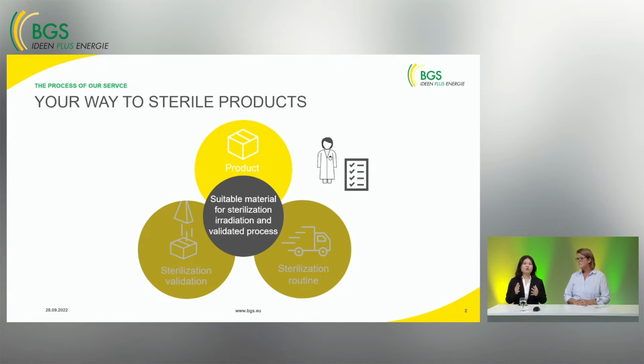We at BGS support you not only to irradiate your product for the routine later on, but also to irradiate your product so that you can establish the sterilization dose and also the maximum acceptable dose. The technical aspects aside, we also need to think how we should process your products so that it is cost and logistically efficient for you. We at BGS have a gamma plant in Wiel, another one in Bruxelles, a 10 MeV e-beam plant in Bruxelles, and another one in Saal an der Donau. And once the technical aspects have been determined, whether e-beam or gamma is more suitable for you, we will then give you a suggestion as to which location you should send your goods to so that it is logistically efficient for you.